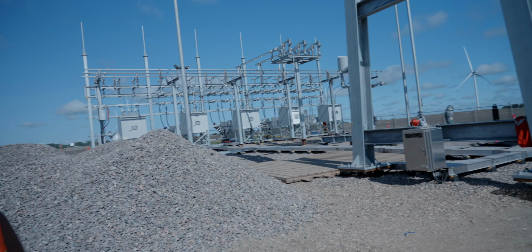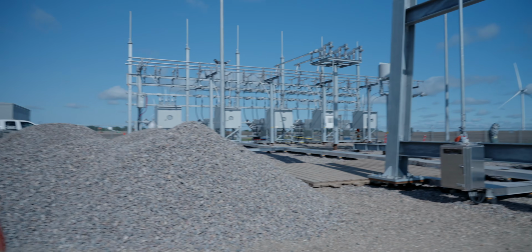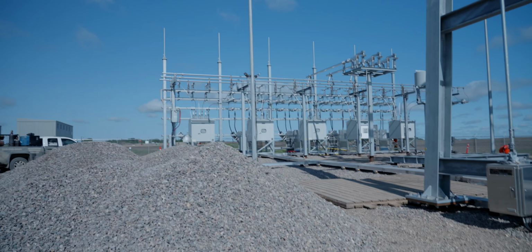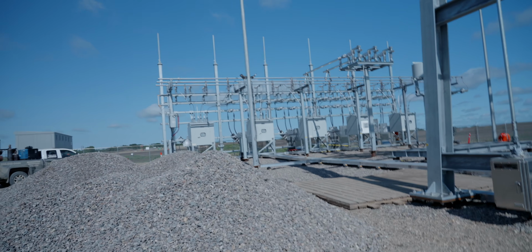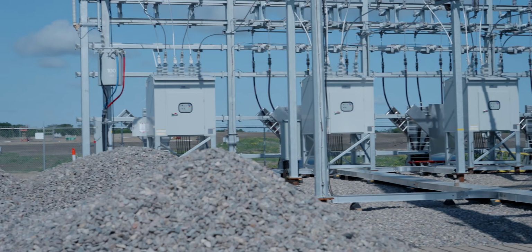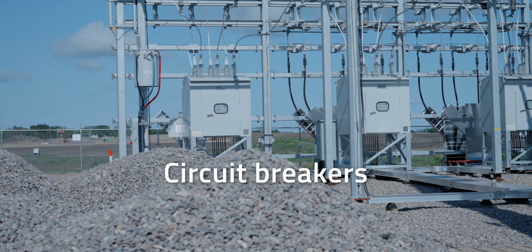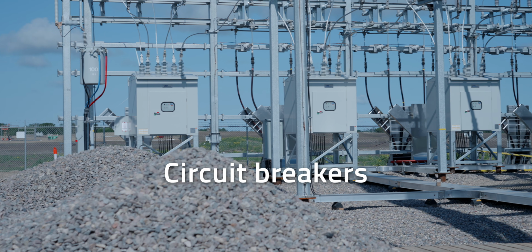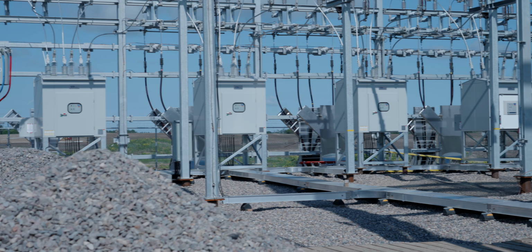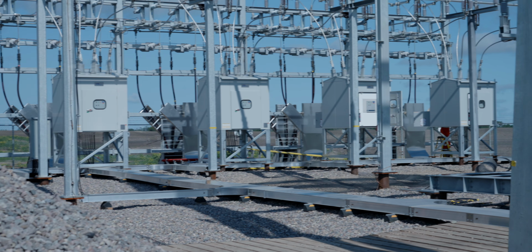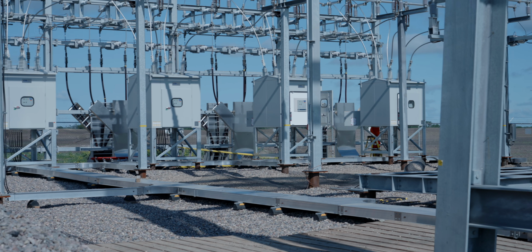What about over there - what is each one of those individual boxes? Those gray boxes are all circuit breakers. There are 5 of them. We have 8 circuits feeding from the turbines into the substation, with 2 circuits going to each of 4 breakers. The 5th breaker is for the capacitor bank, which helps filter the power.